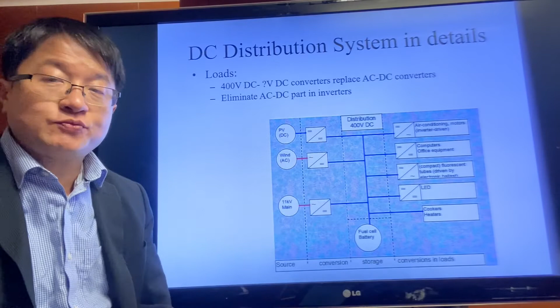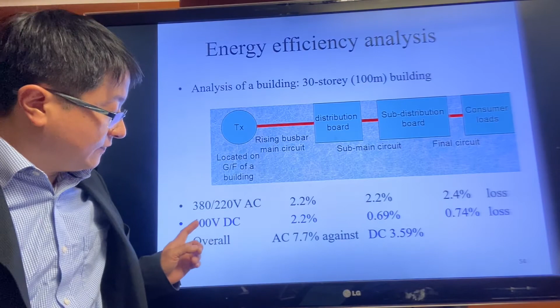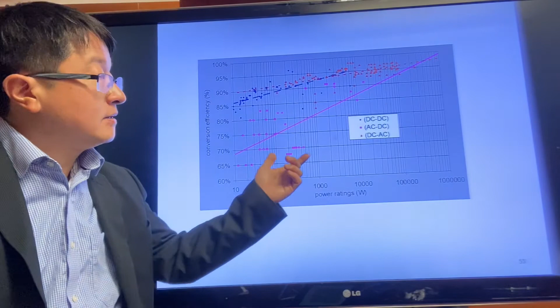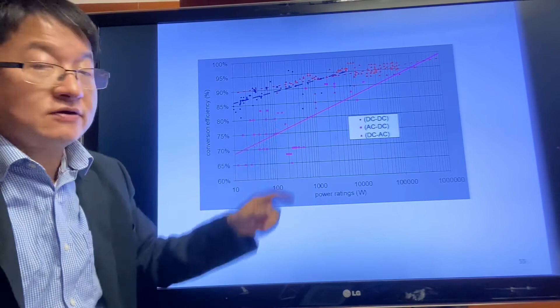Compare with the 220 volt AC with a 400 volt DC power distribution system from the transmission side to the consumer side throughout the distribution network. So the loss across these transmissions for AC is finally 2.4% loss, but for DC 400 volt is 0.74%. Okay. And this diagram showed us that the higher the power rating, then this saving will be more significant. When the power rating is high, then the conversion efficiency for DC to DC is higher. In general, no matter in which power rating segment, DC to DC conversion is always higher than AC to DC conversions or DC to AC conversion.